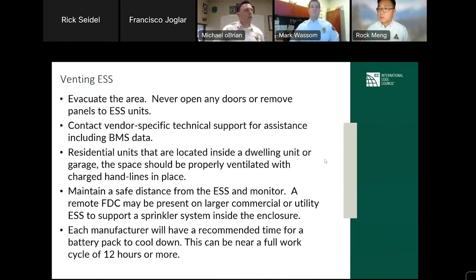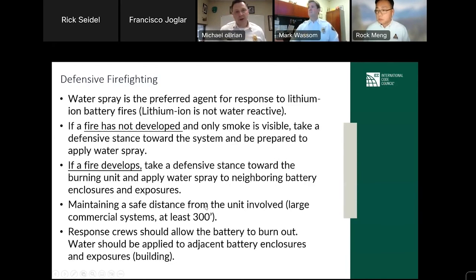Next slide. As we start to talk through this defensive firefighting, water spray is really the preferred agent when we get into the fire response. If the fire's not developed and only smoke is visible, we go back to taking that defensive stance. If you have hydrants or a rural water supply, secure it, get lines in place, and we are probably going to be in a waiting game until we can get the experts on scene to aid our response crews. If a fire develops, take that defensive stance toward the burning unit and apply it to the neighboring units. In many cases, what we're seeing is that adequate safe distance is somewhere in excess of 300 feet. And again, you can see one more time where we're going to say, hey, let this thing burn out.